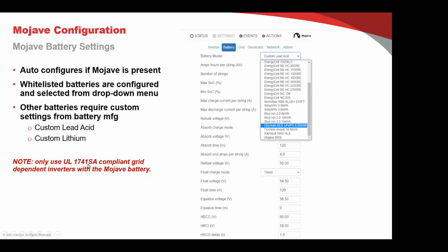So for now, only use the 1741 SA compliant grid dependent inverter with Mojave. The non-SA units, the ones where the upper end frequency is only 60.5, not 62 hertz, there's no frequency range to control them. They do what we call bang bang charging: they surge up, shut off, turn off for 5 minutes, turn on, surge up. So unless there's lots of power to absorb all that energy, you can get into this bang bang charging. It's just hard on the battery, and that's why I don't recommend doing AC coupling with an inverter like that. Normally, even with a Mojave battery, we're saying that we need to have full regulation over that grid dependent inverter. We need to be able to curtail it when we need to. And so that is a requirement with Mojave, that your grid dependent inverter is SA compliant.